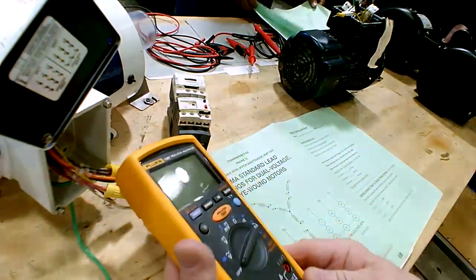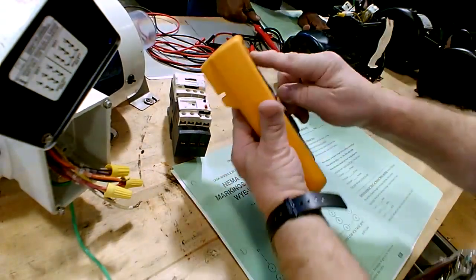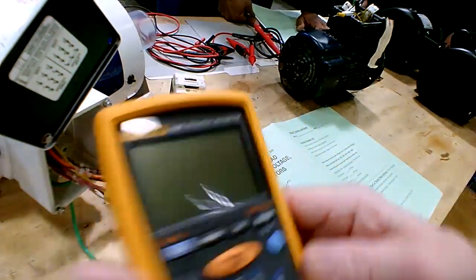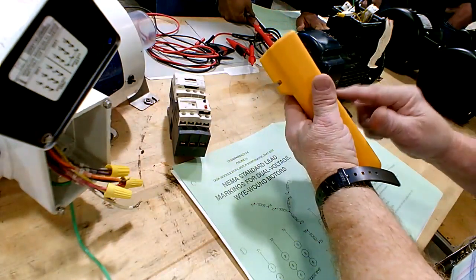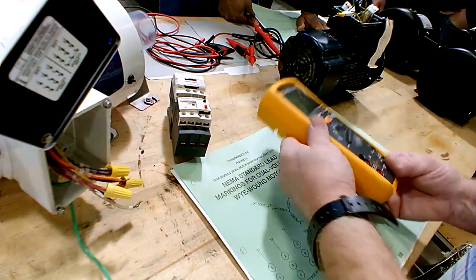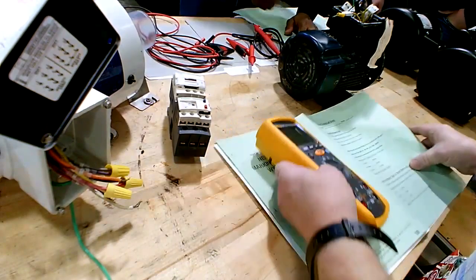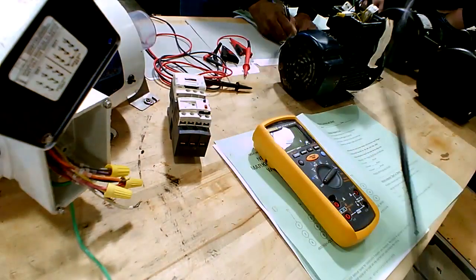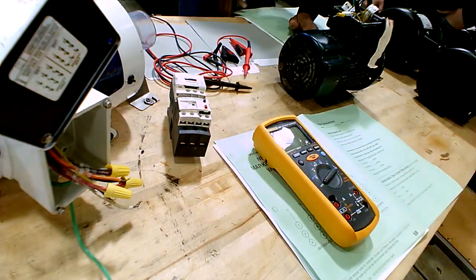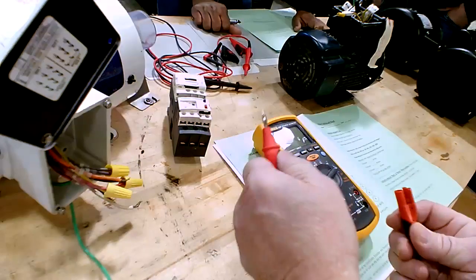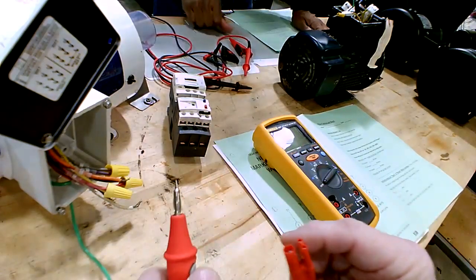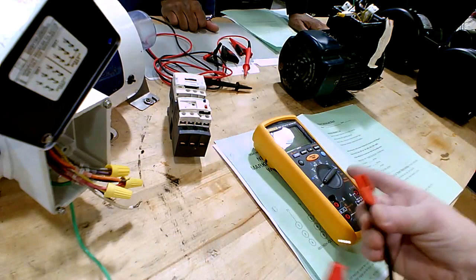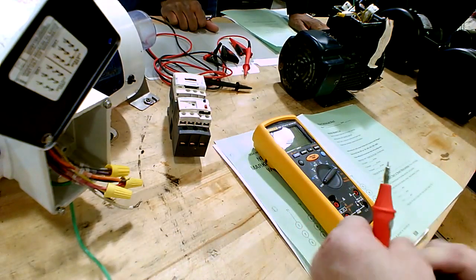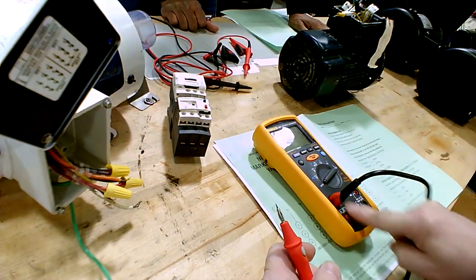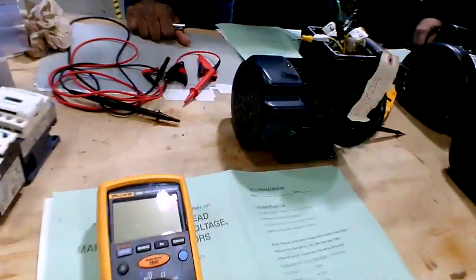Now, if you look closely here, this meter is called an insulation multimeter. It's a Fluke 1587. It does insulation testing plus a lot of other things. It's a great meter. And the way this thing works is like this. There's a special plug here that has a push button on it, and the push button is these two terminals here. When you hit it, it tells the unit to put the high voltage on this line, which comes in through that. So it's a special plug that goes in the orange connection there for insulation testing.